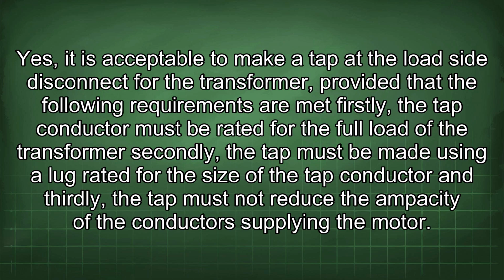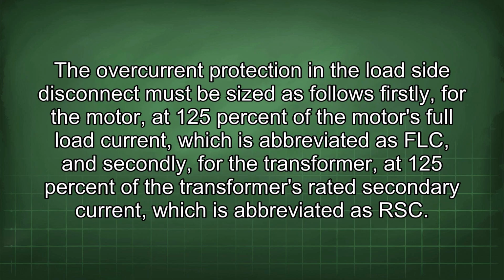requirements are met. Firstly, the tap conductor must be rated for the full load of the transformer. Secondly, the tap must be made using a lug rated for the size of the tap conductor. And thirdly, the tap must not reduce the ampacity of the conductors supplying the motor. The overcurrent protection in the load side disconnect must be sized as follows.